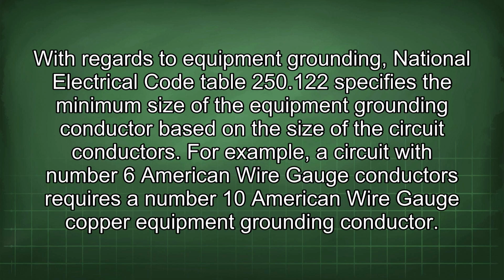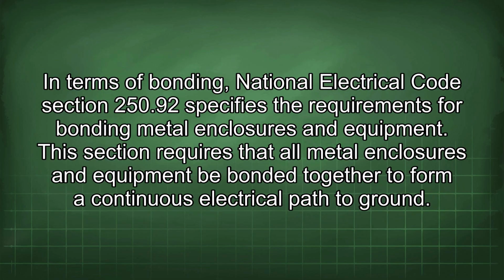With regards to equipment grounding, National Electrical Code Table 250.122 specifies the minimum size of the equipment grounding conductor based on the size of the circuit conductors. For example, a circuit with number 6 American wire gauge conductors requires a number 10 American wire gauge copper equipment grounding conductor. In terms of bonding, National Electrical Code Section 250.92 specifies the requirements for bonding metal enclosures and equipment. This section requires that all metal enclosures and equipment be bonded together to form a continuous electrical path to ground.